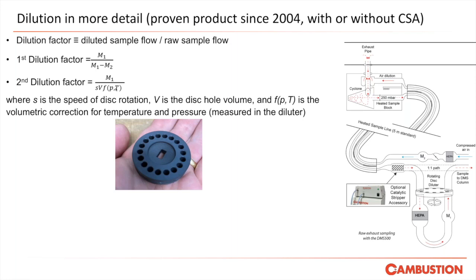Quick word about the rotating disc diluter. Here is the actual dilution disc in place in my hand. Recently, someone suggested that those discs might wear up very quickly. In fact, they don't. We went to some trouble to choose a slippery enough material that really doesn't happen. In fact, before this webinar, I had a look on our spare parts list, which is on our website. It's not actually listed as a spare part for sale because simply it doesn't really wear out. I mean, we don't even change it routinely at service. So they last for many, many years and have proven to be very reliable over these last 16 years.